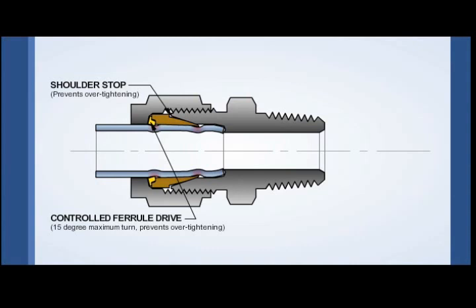More importantly, over-tightening causes the ferrules to bite too deep into the tubing wall, creating stress risers. Inducing too much stress makes the tubing more susceptible to corrosion, and too deep of a bite can lead to a dangerous thin wall condition.